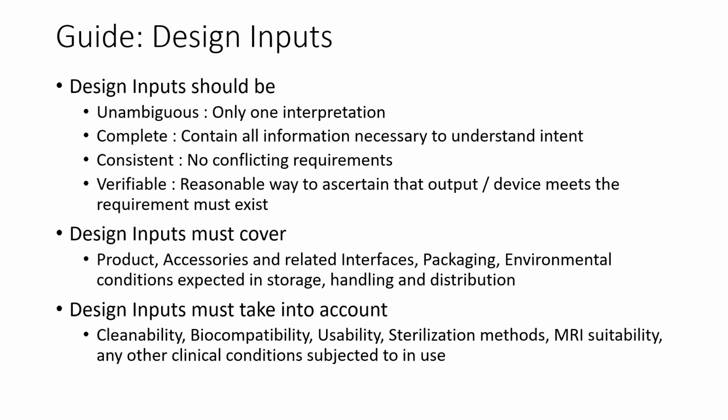And also, since we are in the critical healthcare and device and tech field, aspects like cleanability, biocompatibility, usability, how will the device be sterilized, whether an implanted device would be subjected to an MRI scan, the patient would be subjected to an MRI scan, so what would be the effect, and any other clinical conditions. All of this would form part and parcel of a design input.